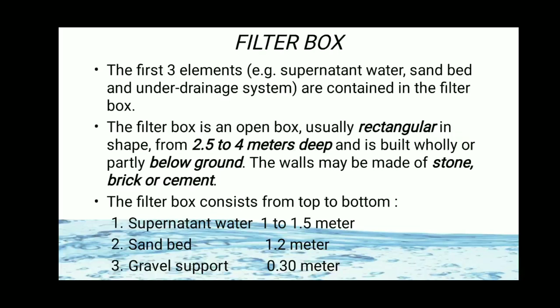Filter control. After the under drainage system there are some valves which control the filtration rate. The purpose of this device is to maintain a constant filtration rate. And there is one meter which measures the bed resistance. It is called the Venturi meter. When the resistance builds up, the operator opens the regulating valves to maintain a steady rate of filtration. When the loss of head exceeds 1.3 meter, the filter is ready for cleaning.